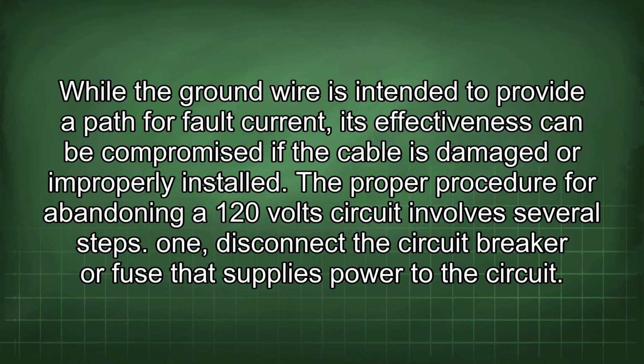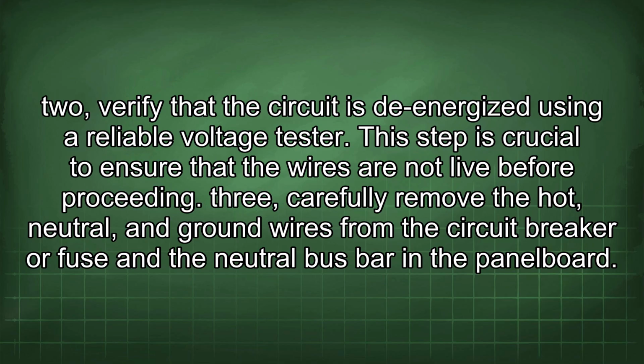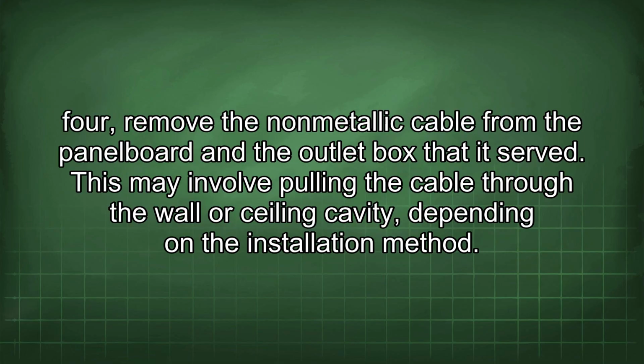The proper procedure for abandoning a 120-volt circuit involves several steps. 1. Disconnect the circuit breaker or fuse that supplies power to the circuit. 2. Verify that the circuit is de-energized using a reliable voltage tester. This step is crucial to ensure that the wires are not live before proceeding. 3. Carefully remove the hot, neutral, and ground wires from the circuit breaker or fuse and the neutral bus bar in the panel board.